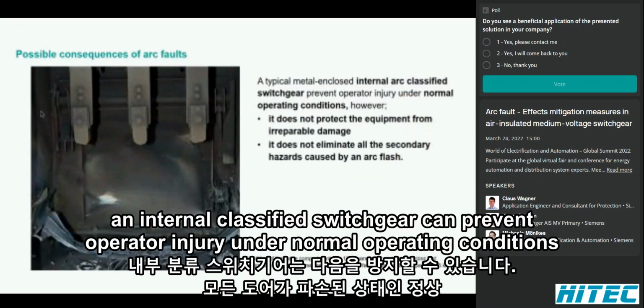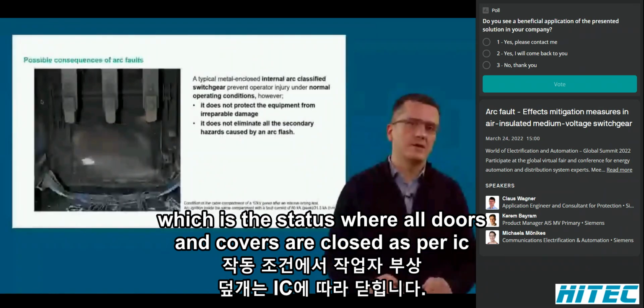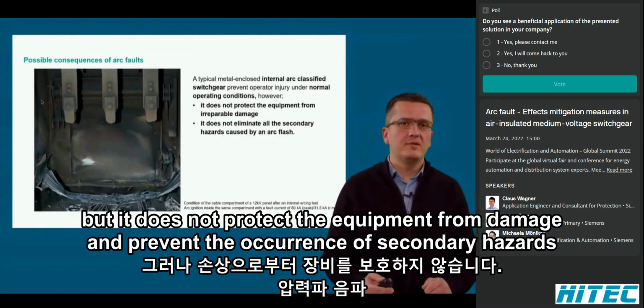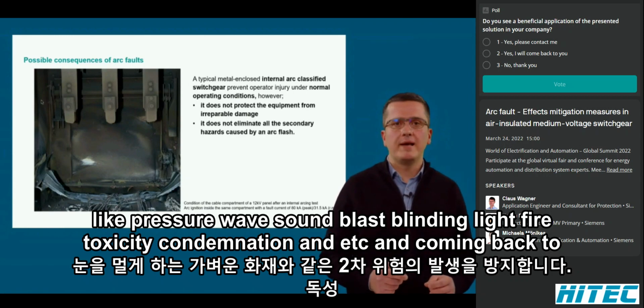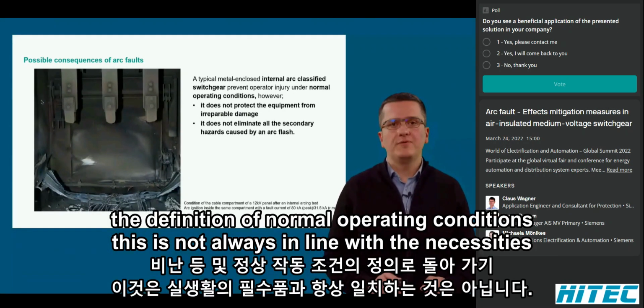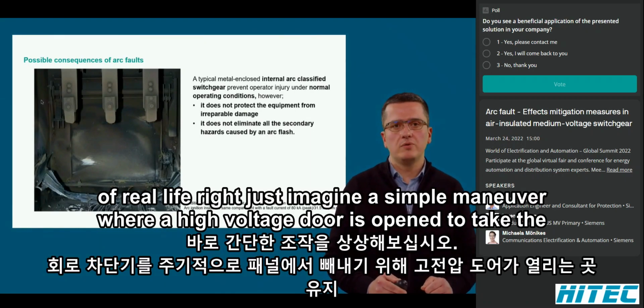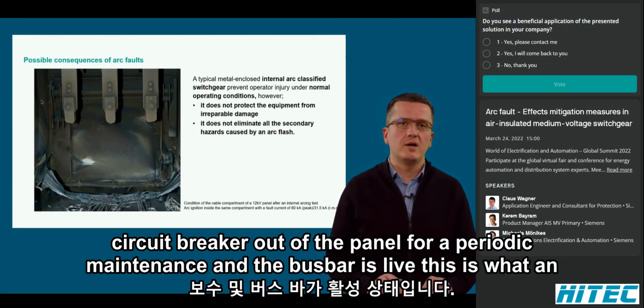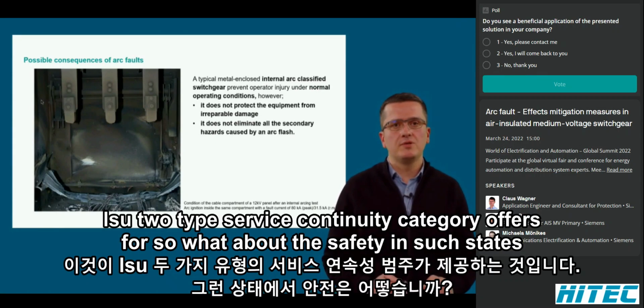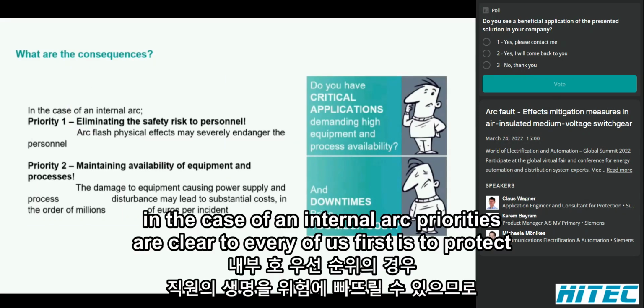An internal arc classified switchgear can prevent operator injury under normal operating conditions, which is the status where all doors and covers are closed as per IEC. But it does not protect the equipment from damage and prevent the occurrence of secondary hazards like pressure wave, sound blast, blinding light, fire, toxicity, contamination, and so on. And coming back to the definition of normal operating conditions, this is not always in line with the necessities of real life, right? Just imagine a simple maneuver where a high voltage door is opened to take the circuit breaker out of the panel for a periodic maintenance, and the busbar is live. This is what an LSC2 type service continuity category offers for. So what about the safety in such status?